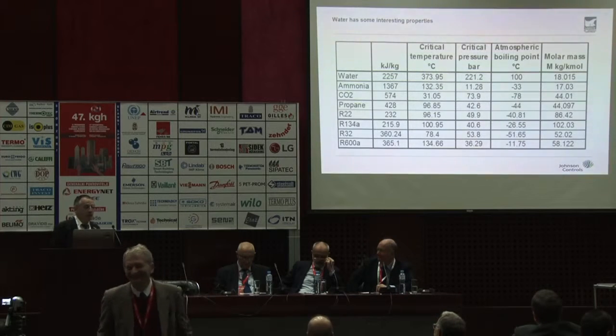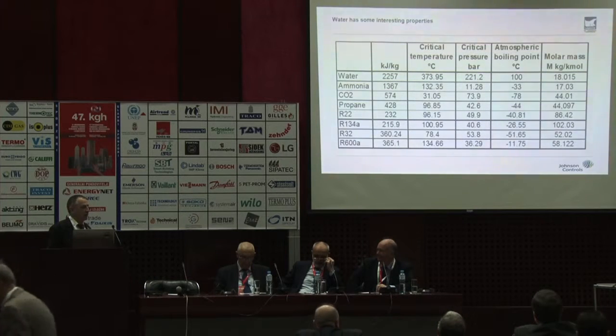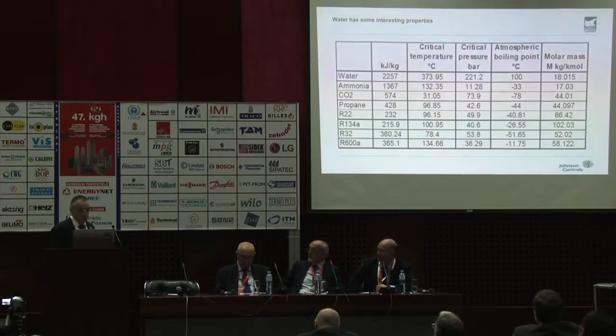The molar weight is very low, which means you have to find other compressors, at least for air conditioning. We cannot use normal turbo compressors because the molar weight is too low, so you need an axial compressor instead of a radial compressor. When it goes up in temperature, water changes a lot in properties, and the molecule becomes heavier, which allows the use of radial compressors at, say, 60 degrees and above. We will see that in a moment.